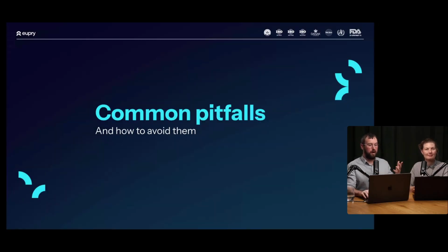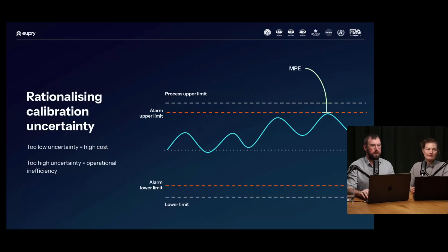So what are some of the common pitfalls we see, and how to avoid them? These are based on our experiences, what we see out there when talking to customers, when we get audited ourselves, and so forth. First of all, not having a rationale behind the calibration uncertainty, or rather the MPE. Remember, the MPE is a global variable that you can set, saying this is the maximum error plus uncertainty we can have for any equipment.